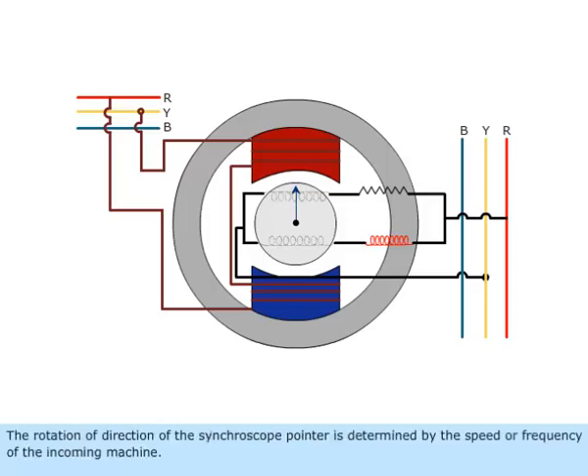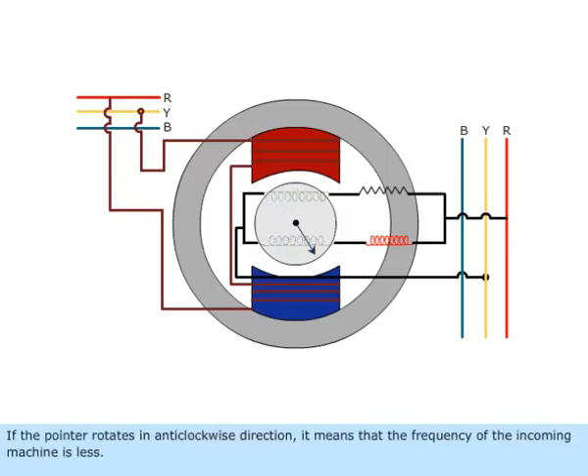The rotation direction of the synchroscope pointer is determined by the speed or frequency of the incoming machine. If the pointer rotates in anticlockwise direction, it means that the frequency of the incoming machine is less. If the pointer rotates in clockwise direction, it means that the frequency of the incoming machine is more.